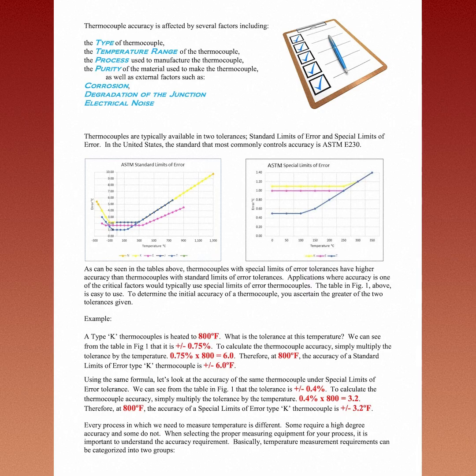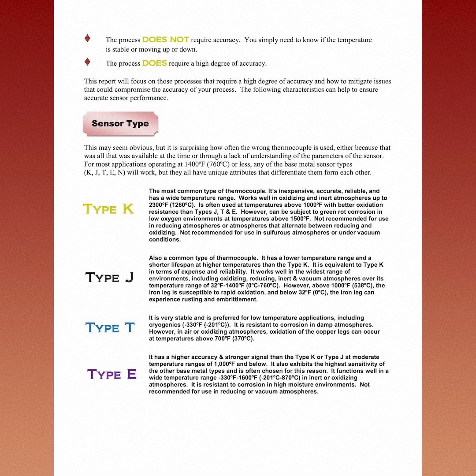Some require a high degree of accuracy and some do not. When selecting the proper measuring equipment for your process, it is important to understand the accuracy requirement. Basically, temperature measurement requirements can be categorized into two groups. 1. The process does not require accuracy. You simply need to know if the temperature is stable or moving up or down. And 2. The process does require a high degree of accuracy. This report will focus on those processes that require a high degree of accuracy and how to mitigate issues that could compromise the accuracy of your process. The following characteristics can help to ensure accurate sensor performance.